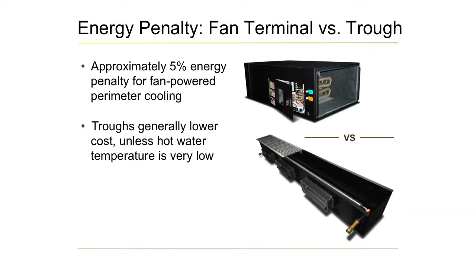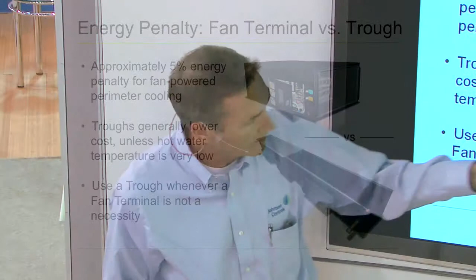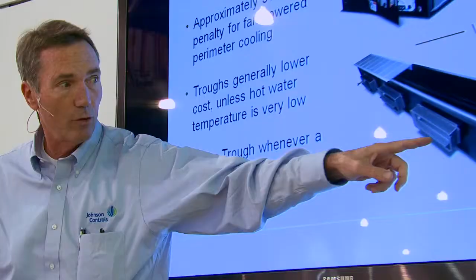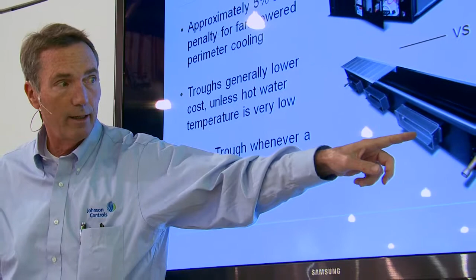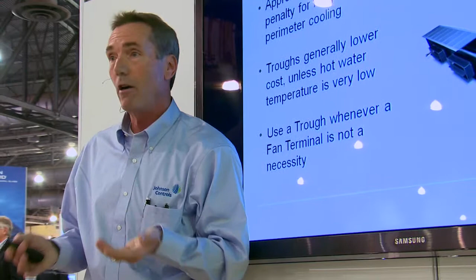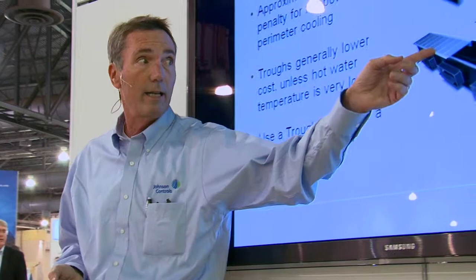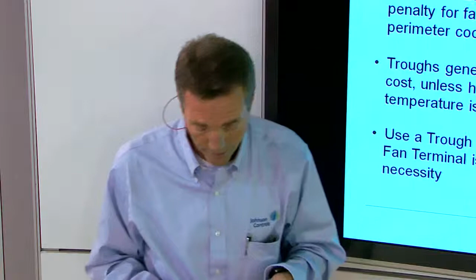And our friends at ASHRAE and CBE up at Berkeley have also said that we're paying about a 5% energy penalty to use these fan-powered boxes, especially if you designed a system, which some do, where you're using a cooling and heating fan, which would be sized for both cooling and heating loads, which would run 24/7. So we're seeing a real shift to these kind of devices, and we're showing one with heating and cooling and VAV with these devices. So a real shift to this, and the other part of the equation here are architects. Architects count, and what architects often like is this nice clean line at a perimeter wall versus a series of round or square diffusers. So our business has probably shifted to better than 50% using that solution. One of the largest platinum jobs in the country is a job for Wellmark out in Des Moines, Iowa, all with that kind of a system on it. So that's a big change.